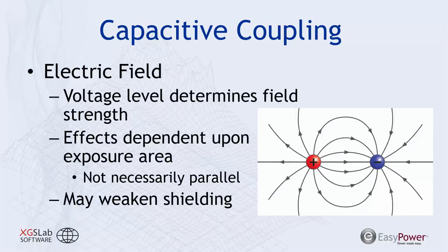Now, our other coupling effect is a capacitive coupling, and this is going to be driven by the electric field. And that's determined from that voltage level, and that's going to drive that field strength. This is not necessarily going to be a parallel object that is going to be the recipient of capacitive coupling. It's really going to be dependent upon the surface area that is exposed to the voltage. But one thing to note is that electric fields don't pass through grounded objects. So if you're having a pipeline or even a rail that's just above the Earth's surface, that electric field is really not going to drive much voltage on that type of recipient.